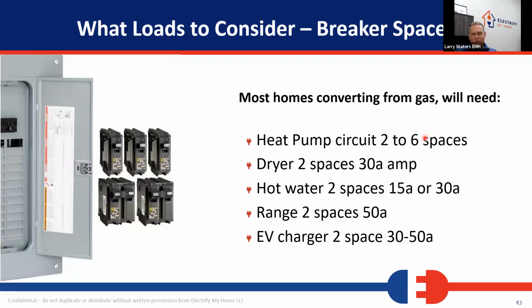So they have to add additional capacity by adding like a strip heating system, a kilowatt heater, and then that takes additional breaker space. Those also need an additional 220 volt breaker in most cases run to the air handler. So it's not uncommon for us to see heat pump systems out there that are using 6 spaces and that require about 60 amps of power be qualified into that load. So dryer is going to take 2, the hot water will need 2. Those heat pump water heaters are also available in 115 volt plug-in where you can just plug it into the wall. They don't have efficiencies that are going to get them a lot of the incentives that are available. And there's also 15 amp 230 volt models available that have smaller backup heaters.